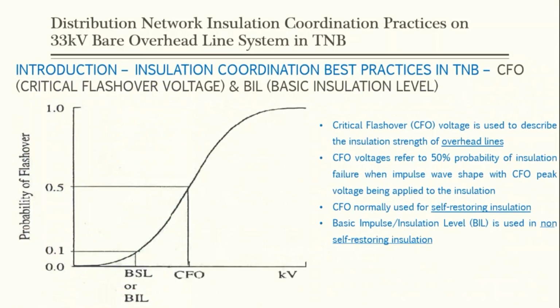Before I continue, let me introduce to you the definition of CFO, critical flashover voltage, and BIL, the basic insulation level. CFO, or critical flashover voltage, is used to describe the insulation strength of overhead lines. CFO voltage refers to the 50% probability of insulation failure when an impulse shape with the CFO peak voltage is applied to the insulation. So it has a probability of 50% failure. And CFO is normally used for self-restoring insulation.